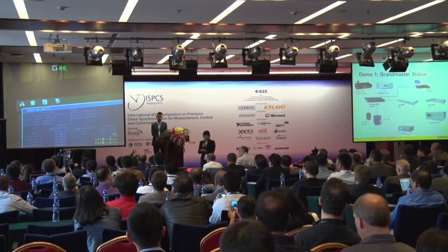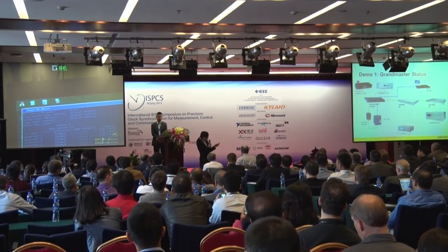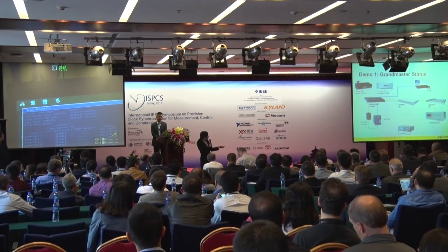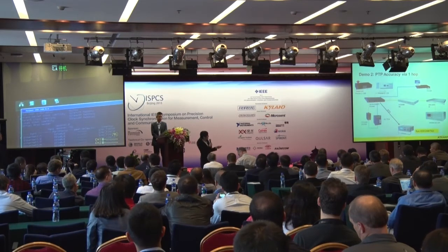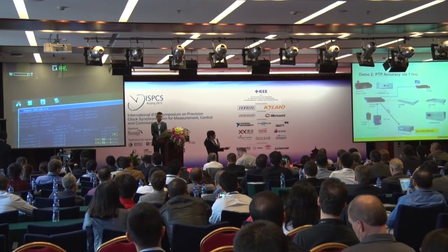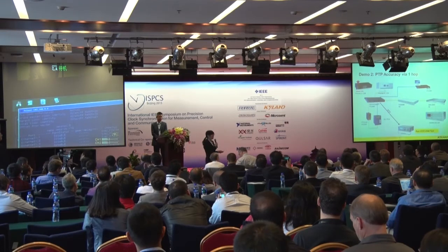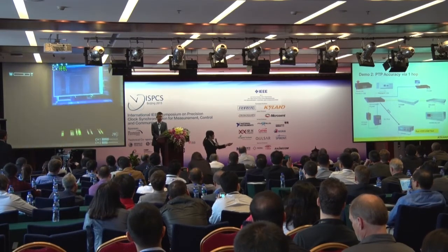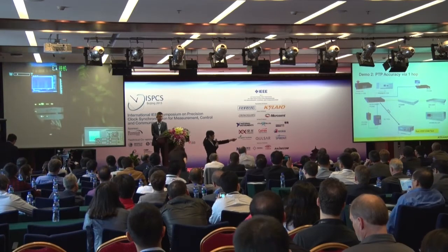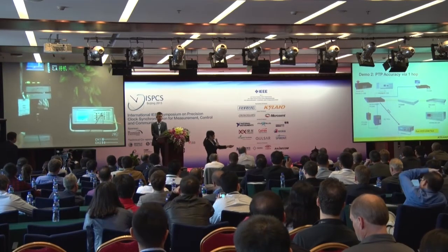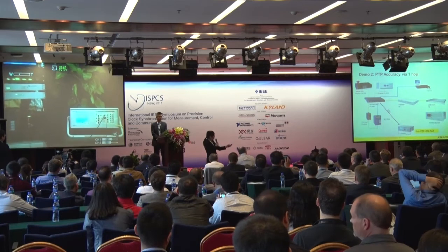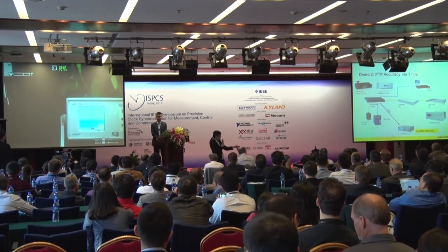And now in this setup, we go to check the PTP accuracy. For the first one, we check the PTP accuracy via one hop, via the Kyland switch here. So we run a test of IEEE1588 in the time tester.